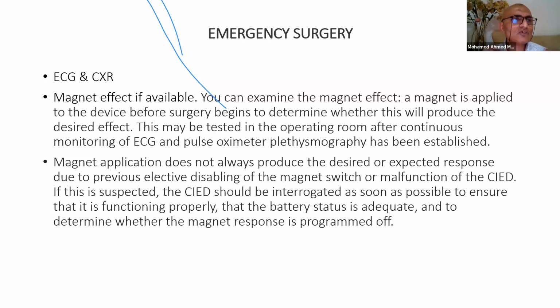After we insert the ECG, the pulse oximetry and the invasive blood pressure, we can put the medical magnet on the device, and we can see its effect on this device. Because as we said, not all devices will respond to the magnet. Sometimes the response of the device to the magnet is turning it off, so when we put the magnet, it will lead to no effect at all. And sometimes the magnet will produce asynchronous pacing, but at a very low rate, which is not suitable.